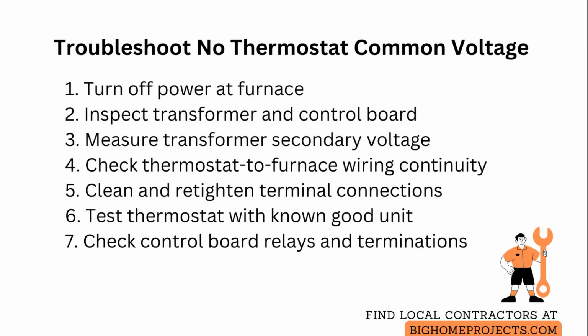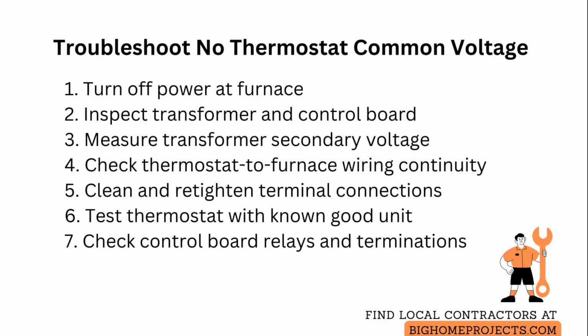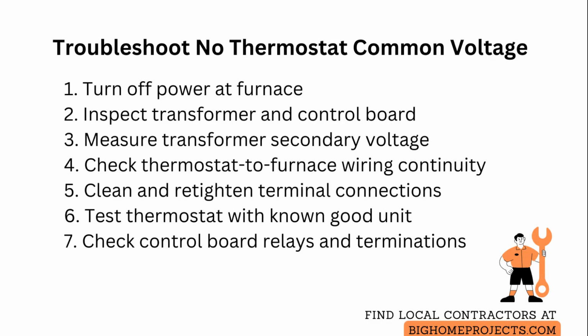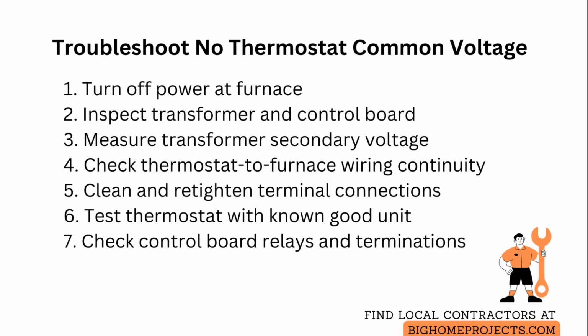Test the thermostat itself by temporarily connecting a known good thermostat or using a continuity test on its common output while calling for heat or cool. A faulty thermostat electronically blocking the common will require replacement.